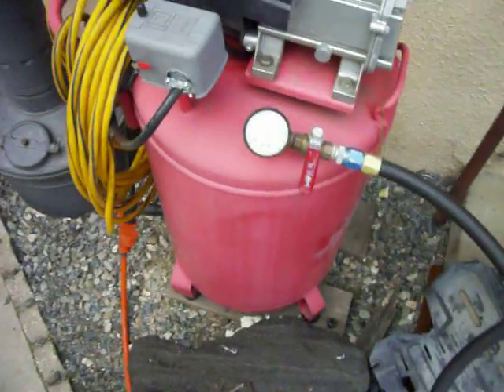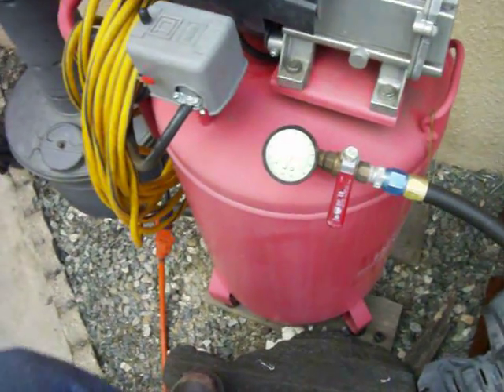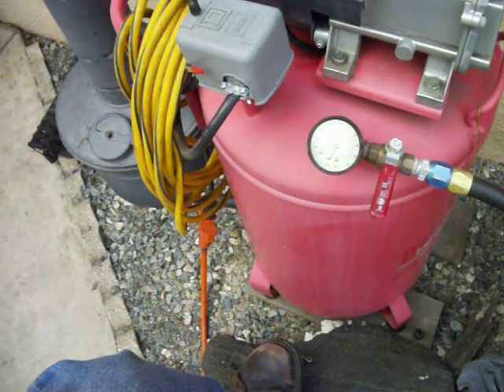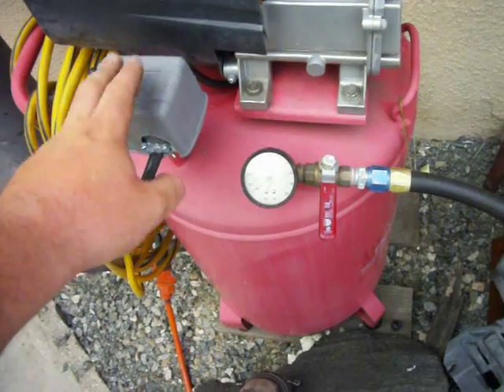Not too bad, but the original PSI on this air compressor was 105. It used to shut off at 100 or 105, somewhere in there. And we bumped it up, and that's what blew the diaphragm out.